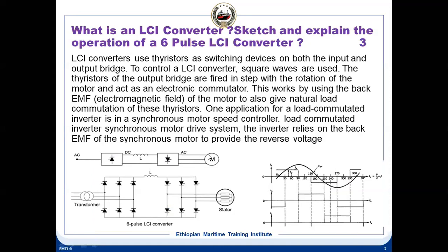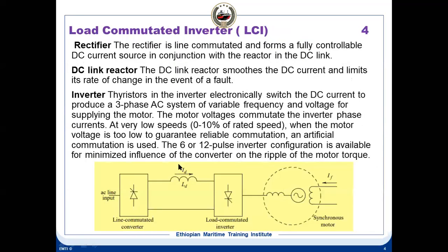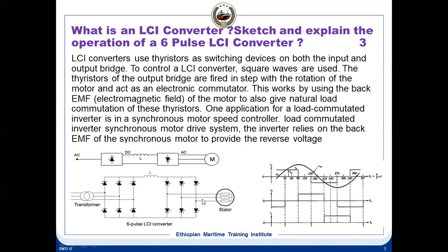Okay. In these converters, we are using thyristors as the switching device on both the input and output bridge. To control this converter, square waves are used. The thyristors of the output bridge are fired in step with the rotation of the motor and act as an electronic commutator. So it is fired in steps, and it converts DC into AC in this way. This is good enough for what is a load commutated inverter, and the explanation of the operation of a 6-pulse load commutated inverter.